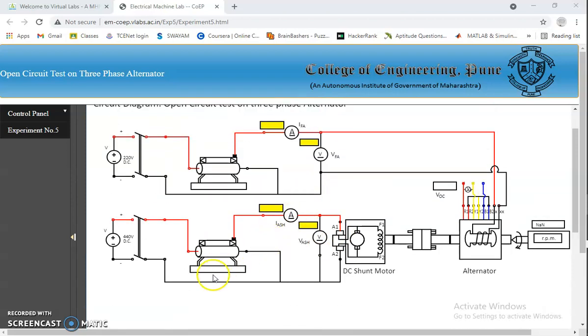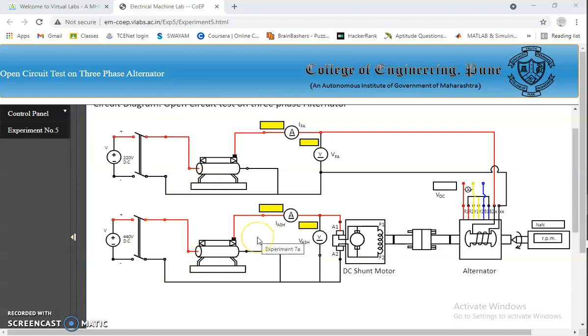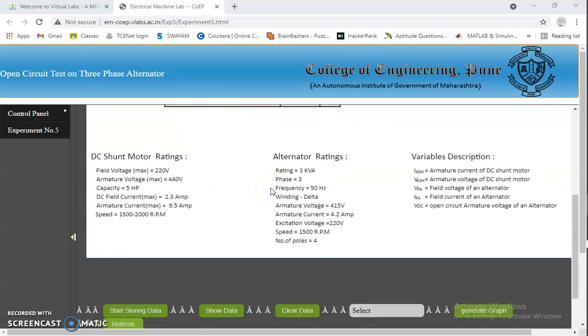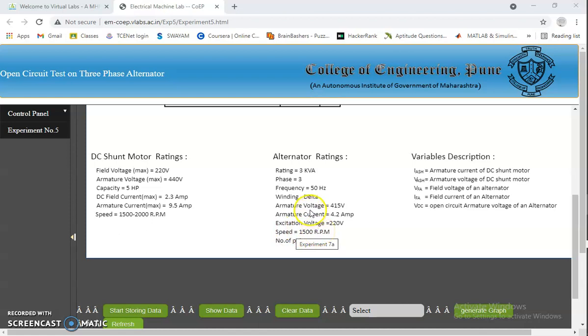This is the armature rheostat of the DC shunt motor which is used to get the rated speed. And by adjusting the field rheostat of the alternator, you are able to get the rated voltage. For conducting this experiment, we need to know the major two ratings. That is speed 1500 RPM and armature voltage 415V. And the DC shunt motor ratings are here.